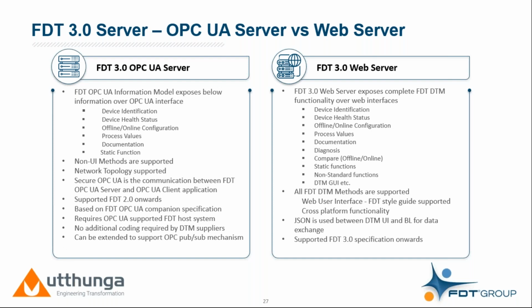The main reason for introducing this static function concept is that usually when an operator wants to read device status values from multiple devices, maybe 100 devices connected to the network, before FDT 2.0 it was required to instantiate the entire DTM just to access this single interface of device health status. This consumed a lot of resources and hit performance in this scenario.